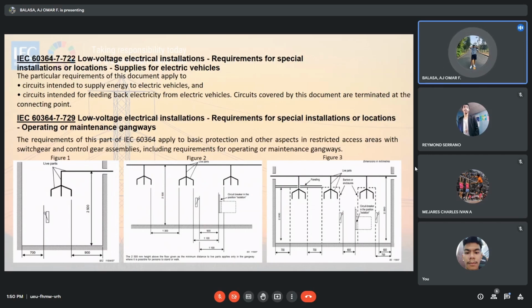The minimum distances are: width of gangway between the wall and live parts, 900 mm; free passage in front of controls, 700 mm; height of live parts above the floor, 2,500 mm. The 2,500 mm height above the floor, given as the minimum distance to live parts, applies only in the gangway where it is possible for a person to stand or walk.